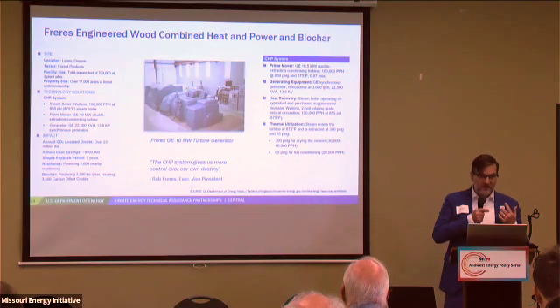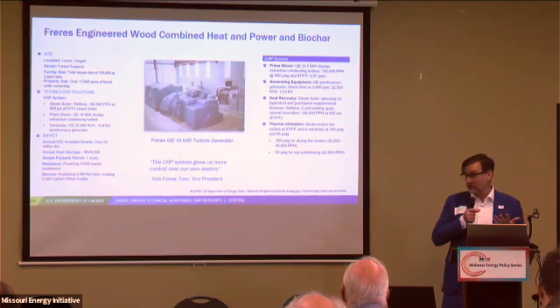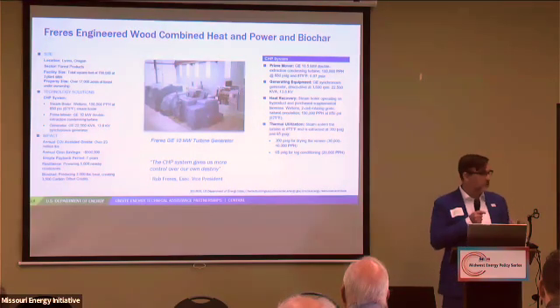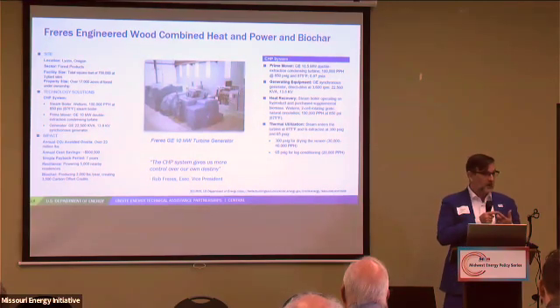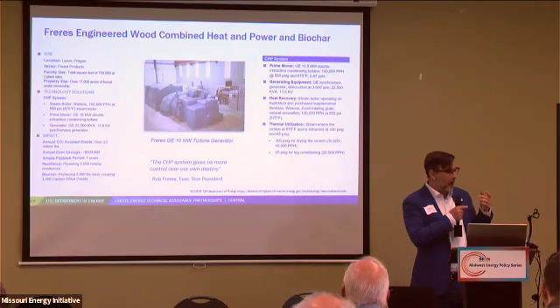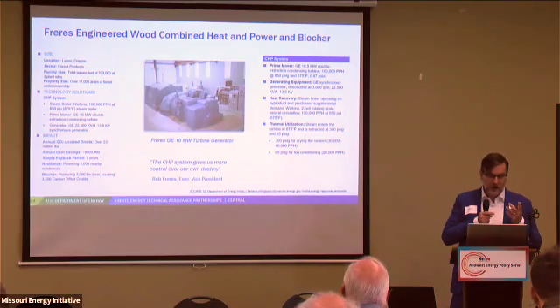That steam was then sent to a GE 10 megawatt extraction, or double extraction, turbine to generate electricity. The steam is extracted at two pressures: 300 pounds to dry veneer, and 65 pounds for log conditioning and to make hot water through steam and hot water heat exchangers.